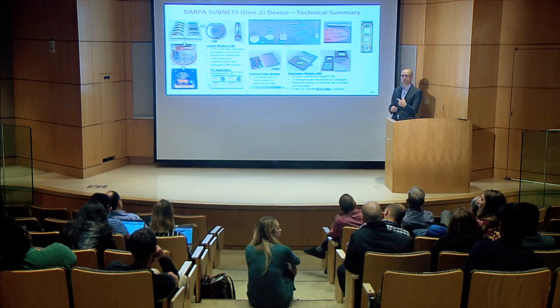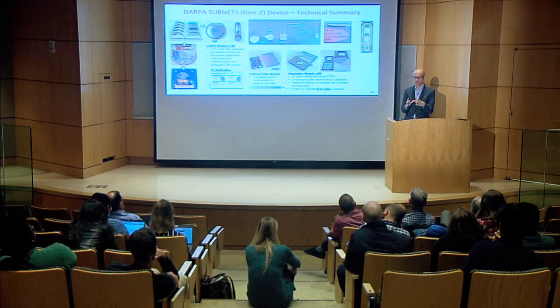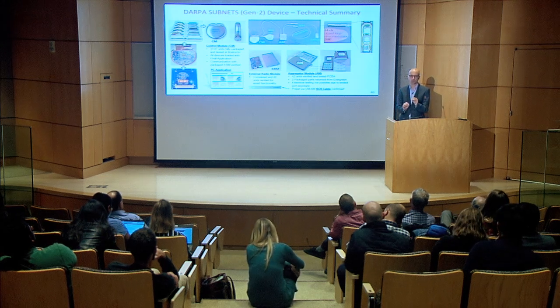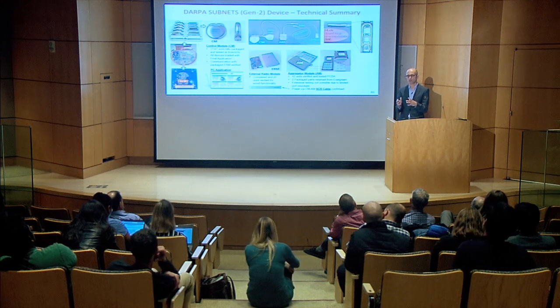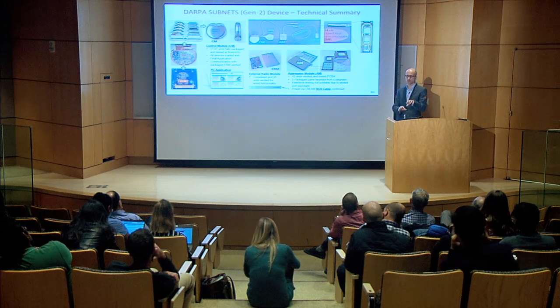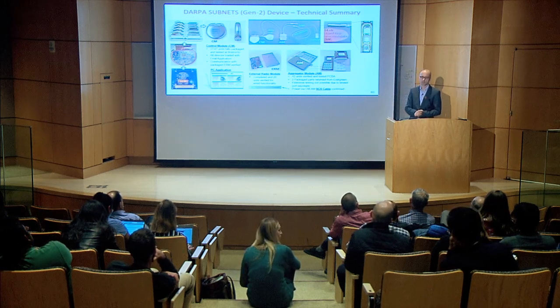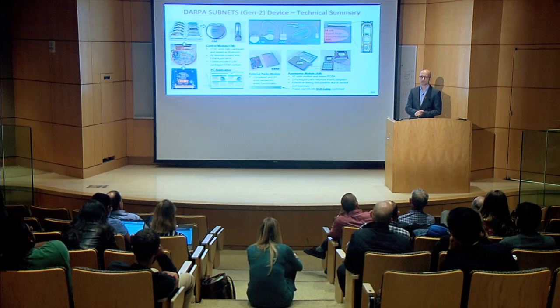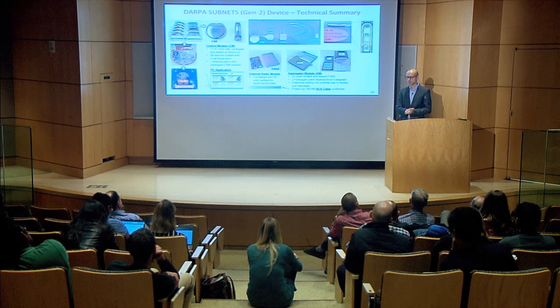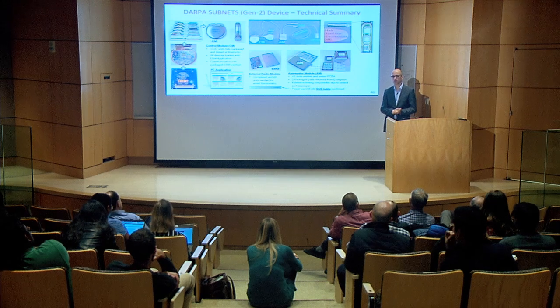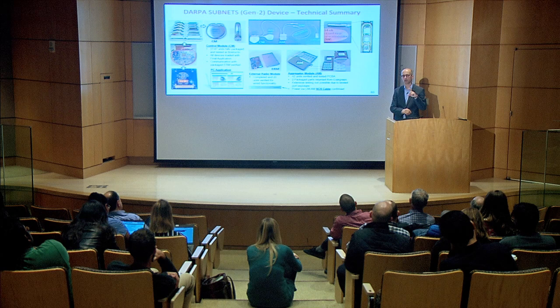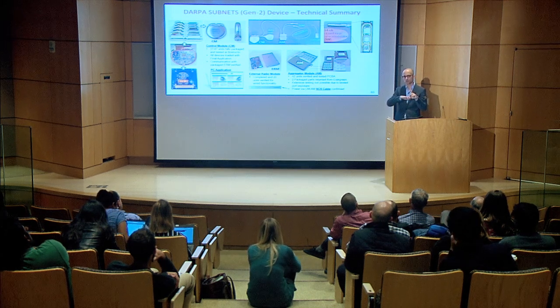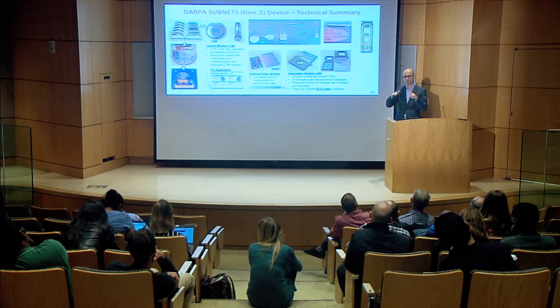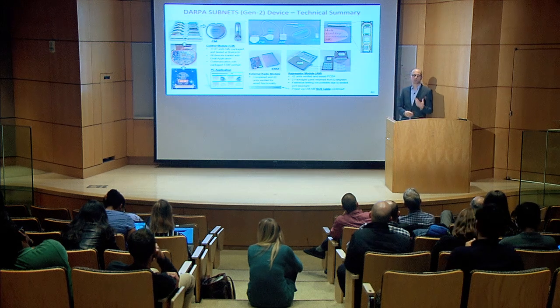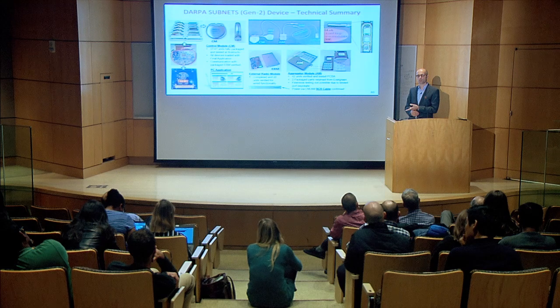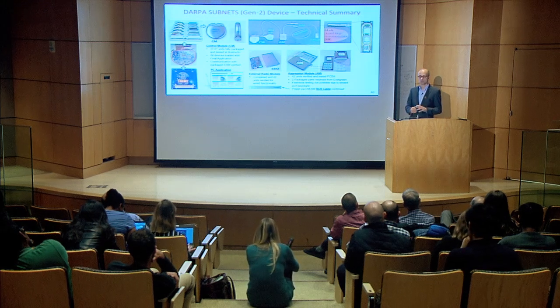And then what you do offline as well, as you extract all of this data, you compute various properties of those channels that are relevant and store them into a matrix model for running real time. And then aggregating all of those features into just one metric, which is an algorithm. You can read papers by Mariam Shanechi from USC who developed the algorithm. But at the end of the day, it comes to one number tell all, which we call integrated mood score. Whatever that means, it's one number that has a lower bound and upper bound. If it is below the lower bound, you invoke stimulation. When it crosses the upper bound, you turn off the stimulation and keep it adapting within those limits to decide when, where, and how to stimulate on 1 or 2 or 4 contacts in a multi-stimulation scenario.